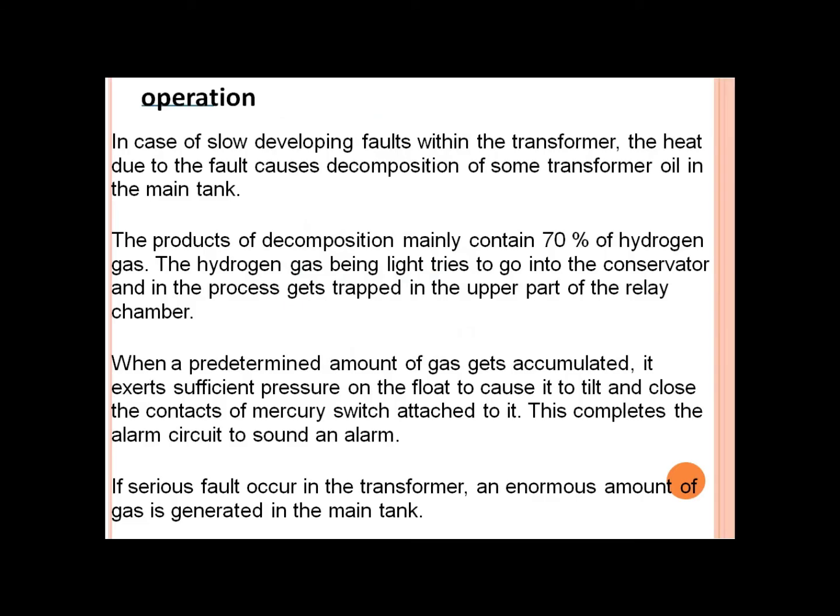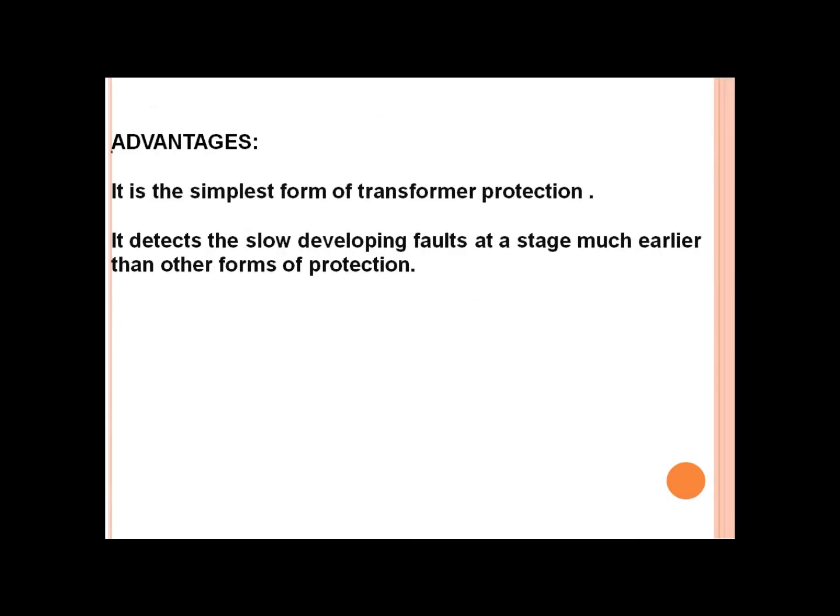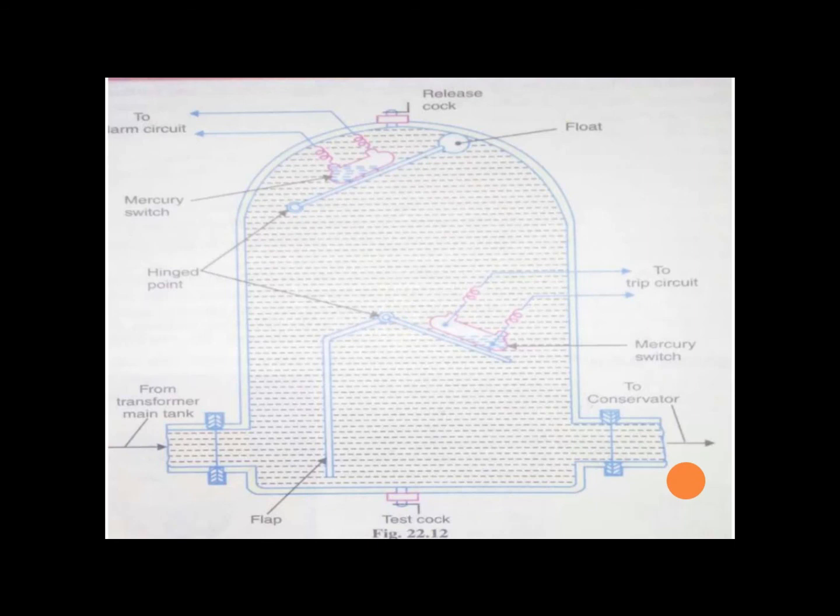What are the advantages? It is the simplest form of transformer protection. It detects the slow developing faults at a stage much earlier than other forms of protection. Sometimes, in the Buchholz relay, there is false detection. Because sometimes, bubbles in the oil cause the upper part of your mercury switch to tilt. So when it is tilted, the contacts are closed, and then there is also an alarm sent when there is bubbling.